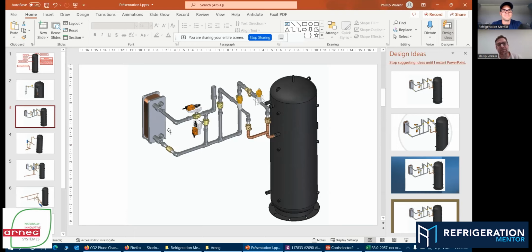This is a typical design where we're using glycol or water or any other means, not flash gas here, to provide additional cooling to the gas cooler outlet side. So gas cooler comes in here, then we're leaving out over here, and we just got a bypass. Simple as that. So if we don't need this additional plate heat exchanger to provide any additional cooling, we're just going to go down like that. We're going to bypass it completely.